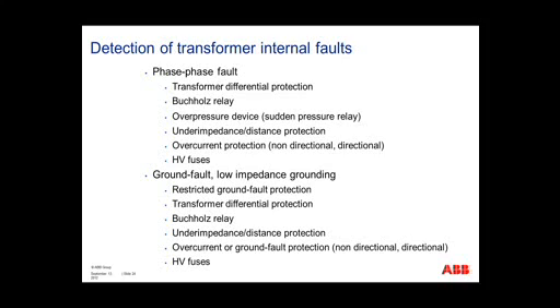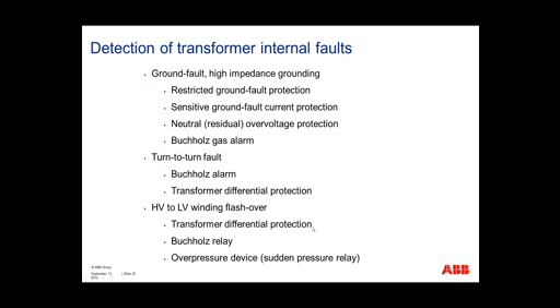For low impedance ground fault, you have your restricted ground fault protection, which we're going to go over later in the discussion. We have transformer differential protection. We have our Buchholz relay, and we have our backup protection of distance protection, overcurrent, and our fuses. For high impedance ground fault, we have our restricted ground fault protection, sensitive ground fault current protection. We have our residual overvoltage protection and our Buchholz gas alarm.